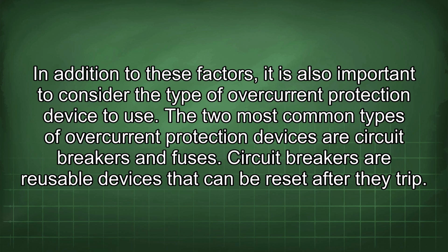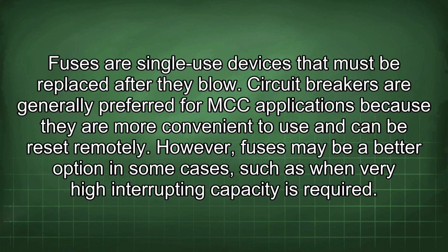In addition to these factors, it is also important to consider the type of overcurrent protection device to use. The two most common types of overcurrent protection devices are circuit breakers and fuses. Circuit breakers are reusable devices that can be reset after they trip. Fuses are single-use devices that must be replaced after they blow. Circuit breakers are generally preferred for MCC applications because they are more convenient to use and can be reset remotely. However, fuses may be a better option in some cases, such as when very high interrupting capacity is required.